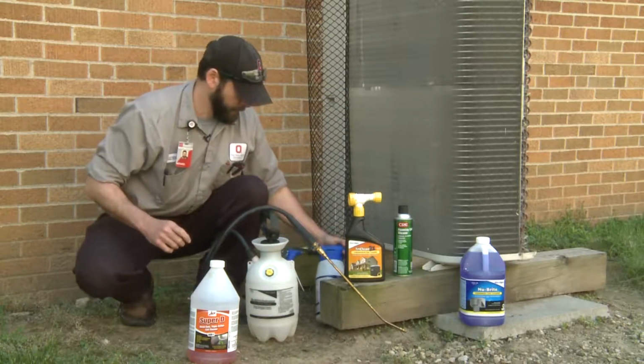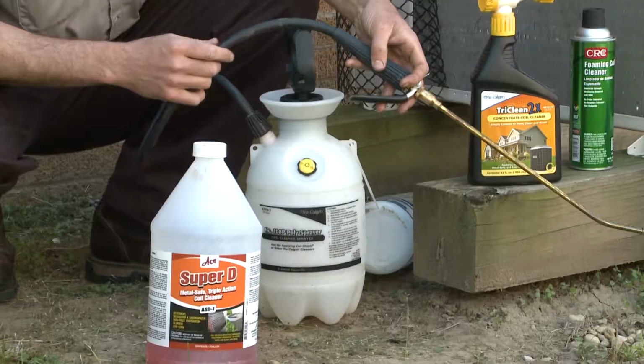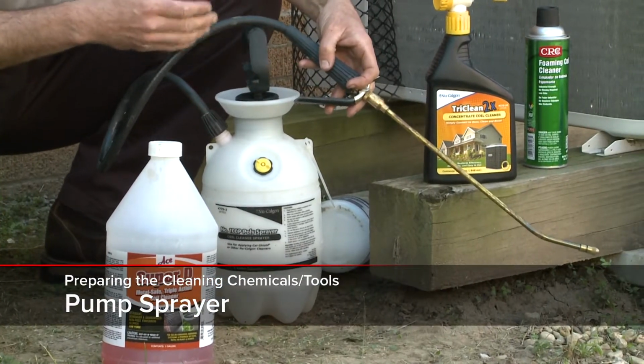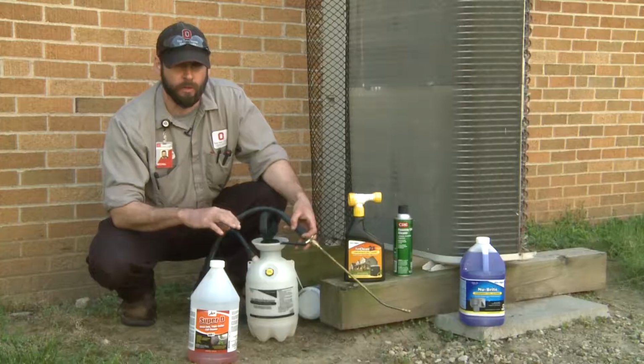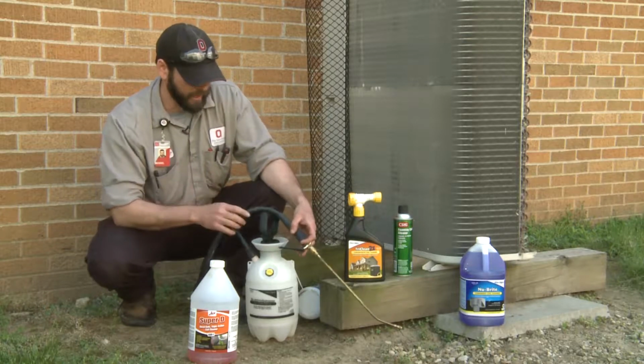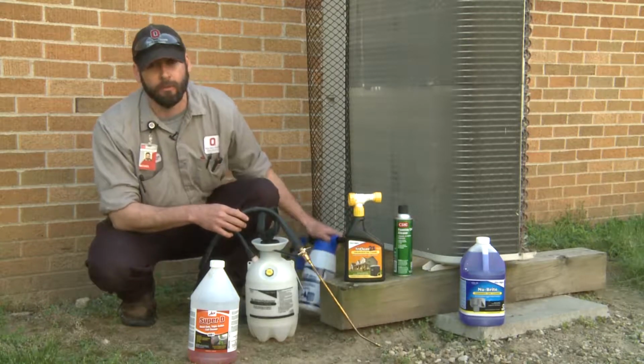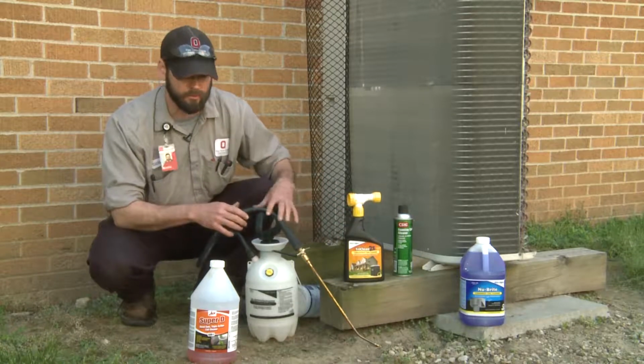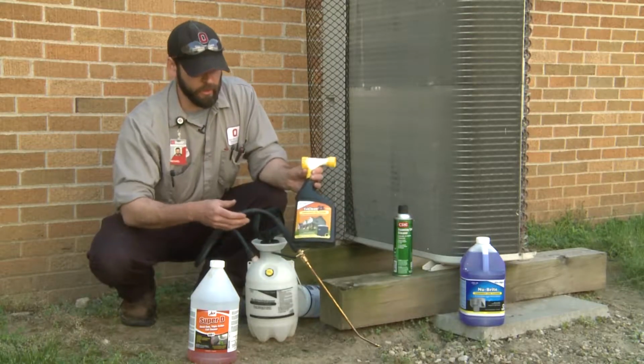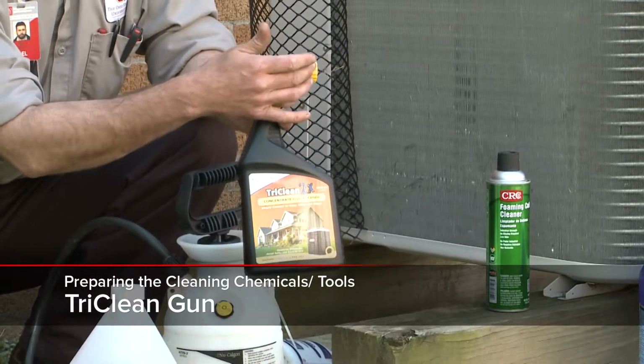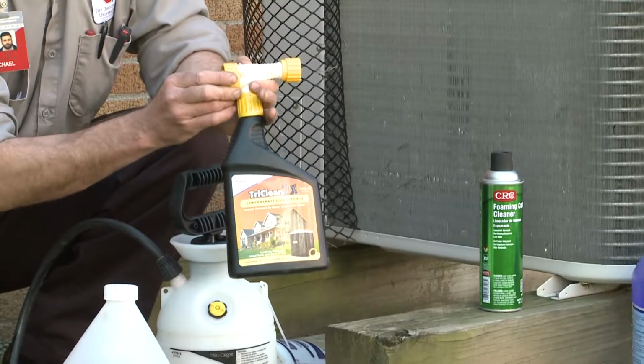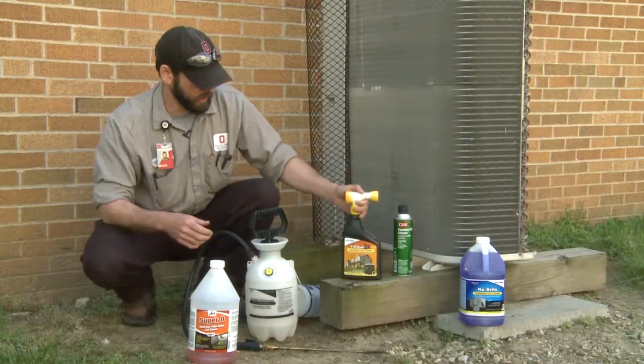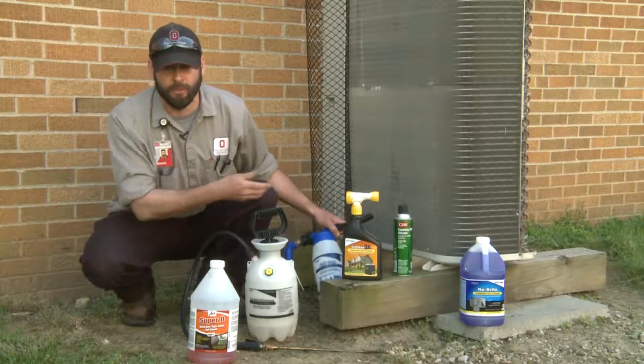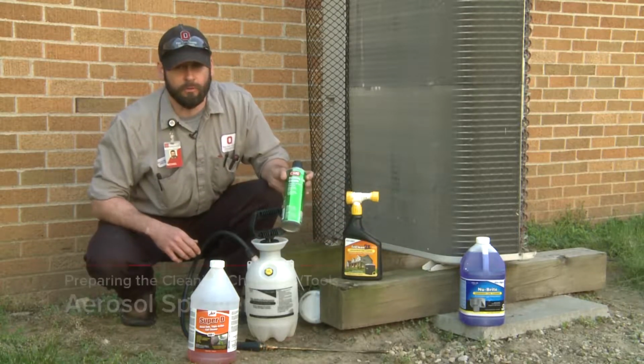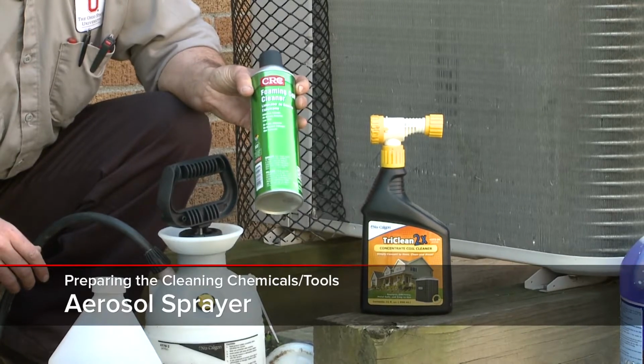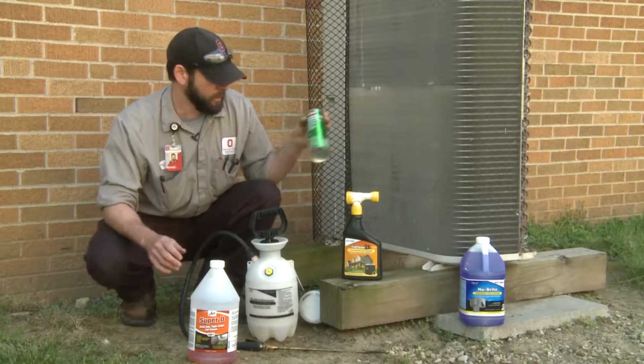Pretty nice, pretty convenient. Another option would be a pump sprayer, and a pump sprayer is good, but the difference here is you need to worry about the ratio yourself. So you need to add the chemical and mix the water, then pump and spray down the coil. Along with that, you're going to have to have a separate hose out there and ready to go so you can rinse the coil with an actual hose nozzle. This is a product where you just buy the solution, connect your hose to the end. It has the option of coil solution or rinse. So it's similar to the gun, but you can't change the ratio on this one. And then you have aerosol condenser coil cleaner or evaporator cleaner, nicer for smaller units and tight spaces.